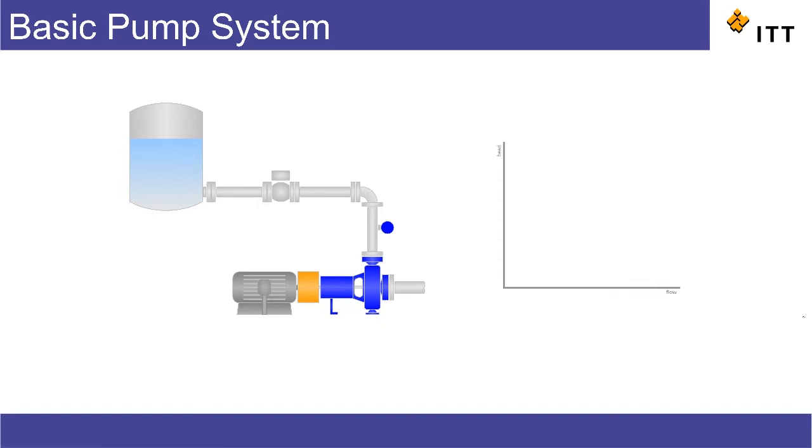The operating point of a pump is defined by the intersection of the system curve and the pump curve. In a simple application like this where you're pumping into a tank, the system curve is made up of two things.